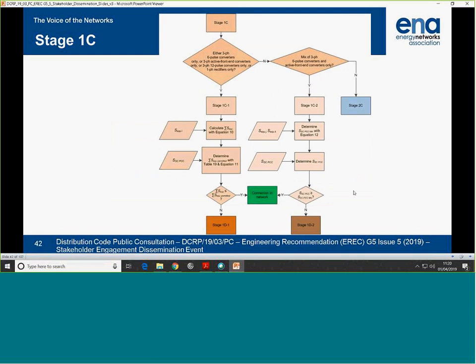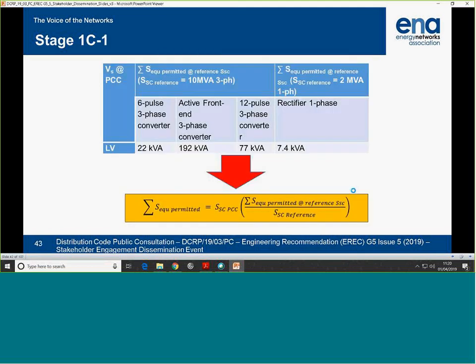The flowcharts are shown here. The way this is split is 1C1, first column, is to do with a single technology type, so you've got 6 pulse or 12 pulse, whereas 1C2 covers the specific case of 6 pulse and active front end. It was possible to do that because the limiting harmonic was the same harmonic order. So the formula that we have is just a simple case of scaling the values.